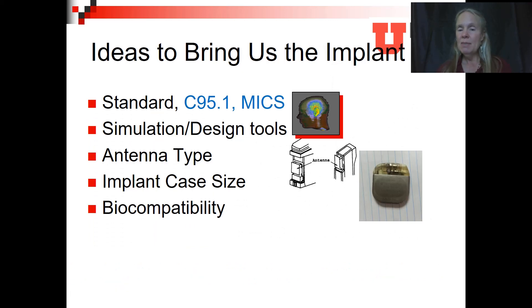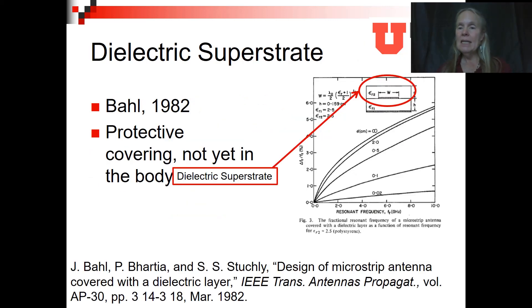With a standard, simulation and design tools, a good antenna type, and an understanding of how the implant case size impacts antenna performance, we next look at biocompatibility. Biocompatibility is seen in two ways: one is the materials the antenna is built from, where plastics and ceramics were appropriate. Also, the SAR guideline — which tells us we can't have super high power right next to the antenna inside the body — led us to use a dielectric superstrate. First seen in 1982, the dielectric superstrate is a protective covering for an antenna. It separates the body so that high SAR values are near the antenna in the plastic rather than in the body itself.